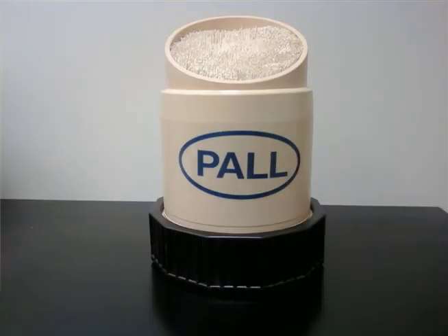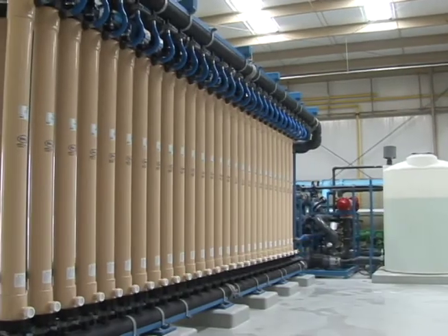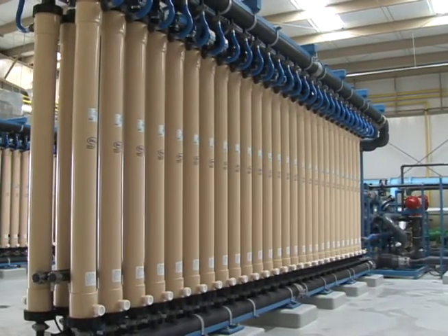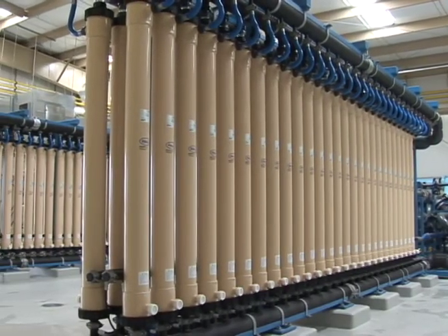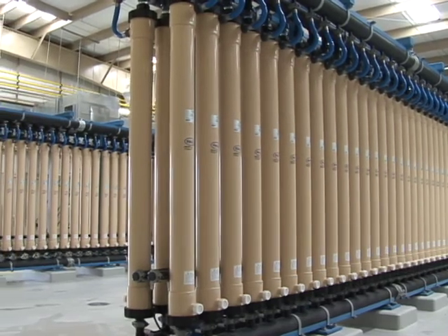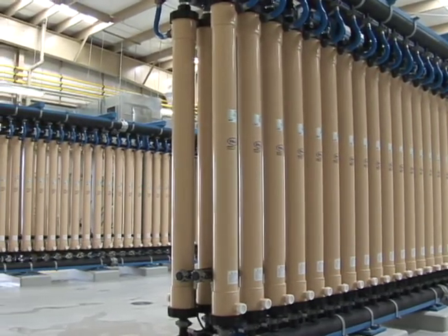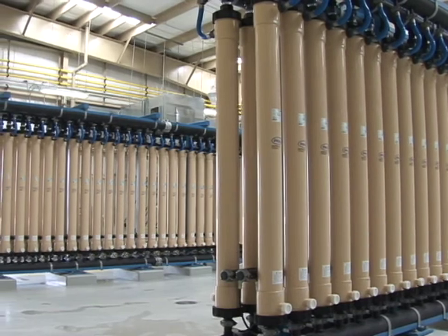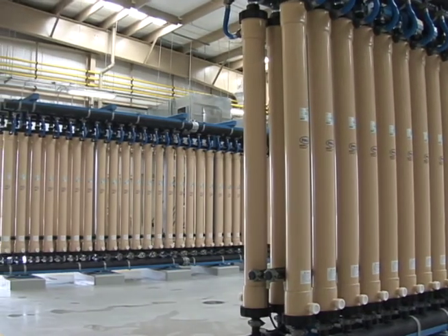After it comes into this building, we send it through membrane filters. What membrane filters are, imagine hundreds of little straws that are about the size of spaghetti. The water goes up inside the straws and then out through the walls of the straws. And the holes in those walls are 0.01 micron, which is smaller than a virus or a bacteria. So it's a physical barrier between anything bad in the water and the public on the other side. So it goes through the filtration process.